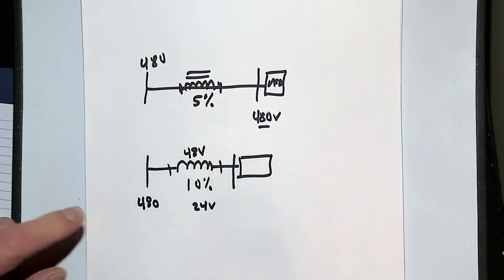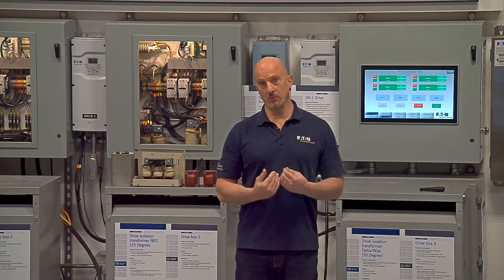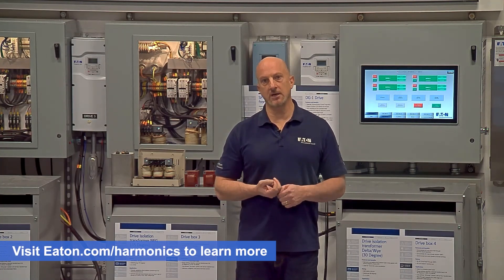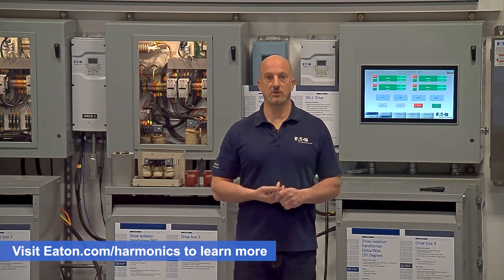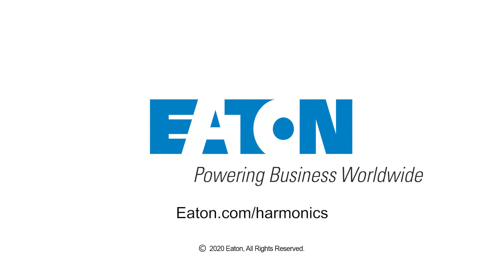So that's why, when we take a look at reactors and we put them in front of a drive, we don't get the same voltage drop as the percent reactance that we add to the system. So again, we would encourage you to use at least 5% on your drive to minimize the harmonic, and the benefit of adding that choke is significant.